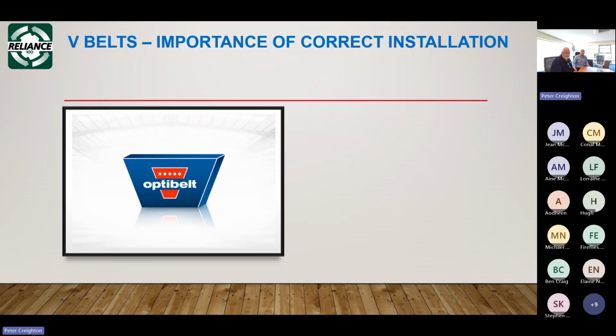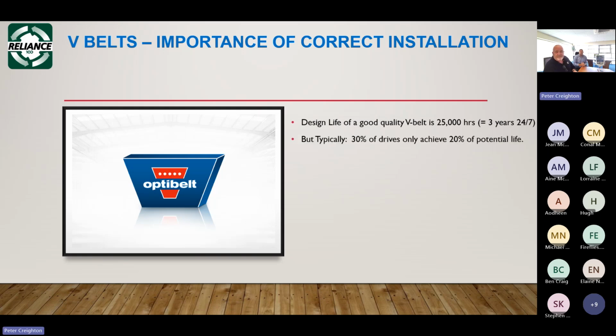V-belts. I'm going to talk a little bit about V-belts and the benefit of V-belts. What people think of a V-belt is that it's a consumable. The design life of a good quality V-belt is 25,000 hours, as I said, 3 years, 24/7. Typically, 30% of the drives only achieve 20% of potential life, and that is down to two things. One is misalignment, which I was on about, your pulleys being aligned correctly, and the other is incorrect tension. 70% of drives, even though you put a lot of time into it, still achieve less than 50% of potential. That is because you can align them properly and tension them properly on day one, but if it's not a certain type of belt and you don't go back to open your AHU every 3 months, which people don't like doing, you start losing efficiency.